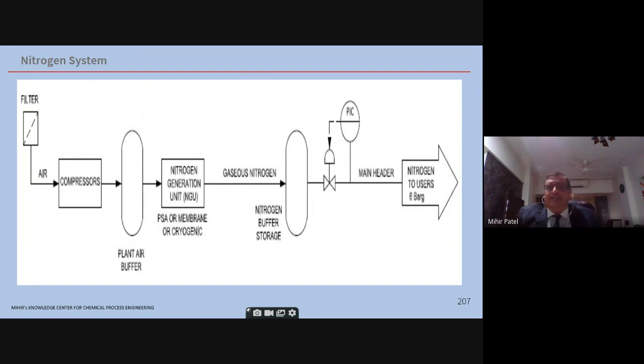Nitrogen is basically produced as follows. The upstream part is similar to a plant air system: you have a filter, compressors, and a plant air buffer. Then you have a nitrogen generation unit, which can be PSA, pressure swing adsorption, or membrane based, or cryogenic based. Cryogenic nitrogen is the best quality. However, cryogenic is very expensive, and it is only used for very, very large capacities. Otherwise, PSA or membrane can be used.